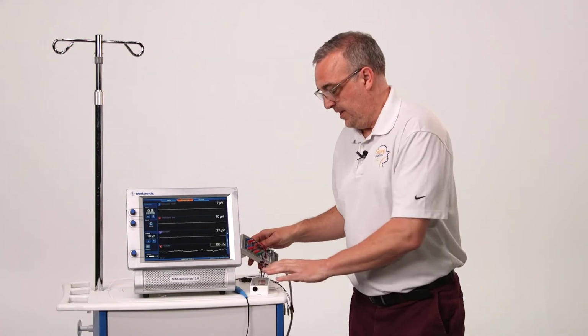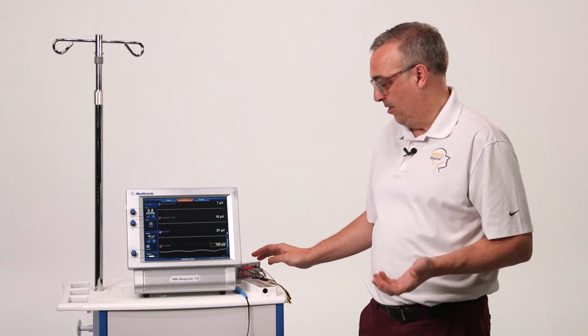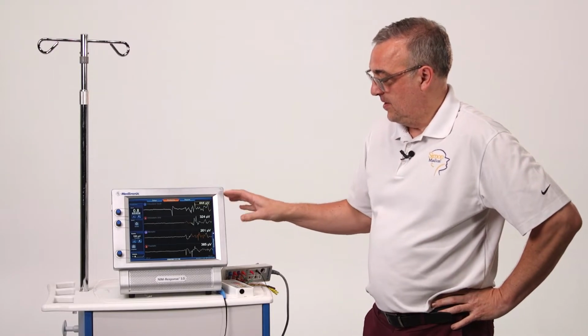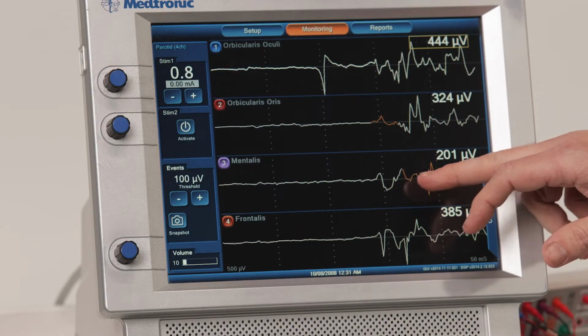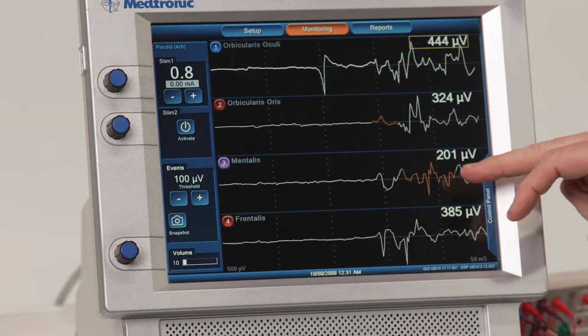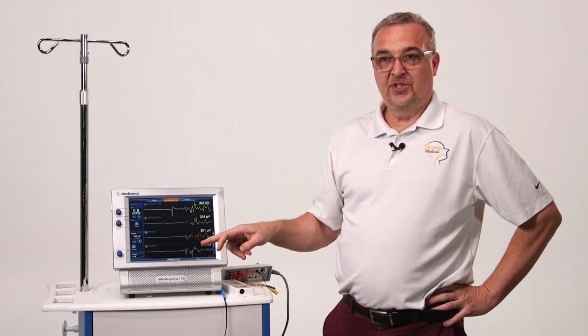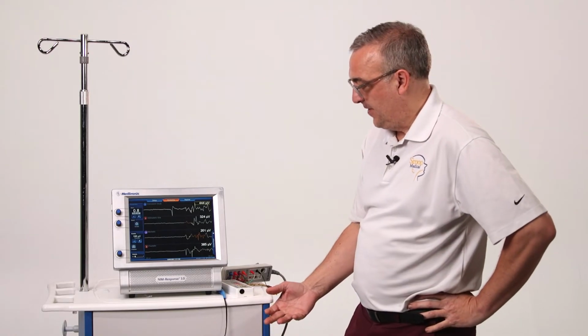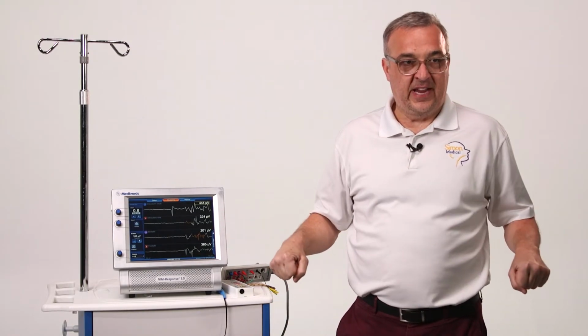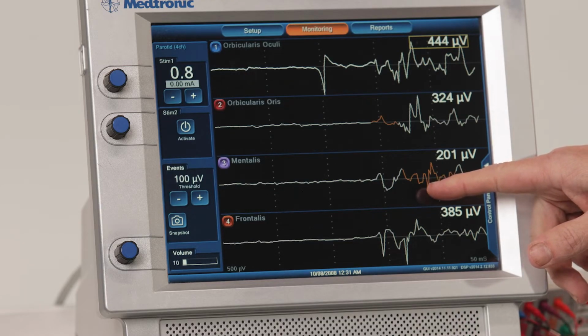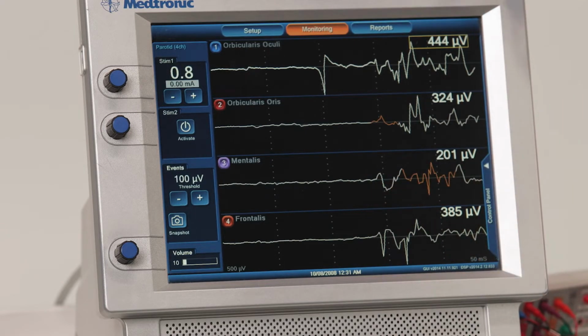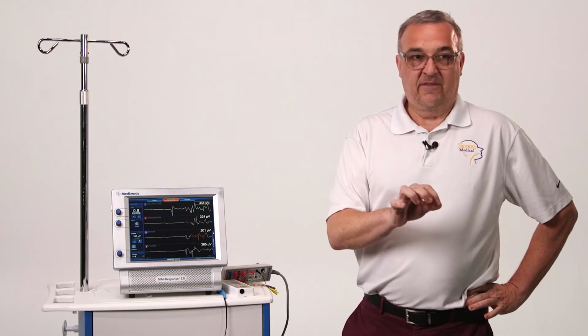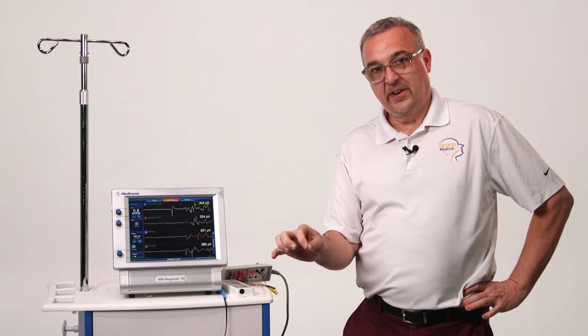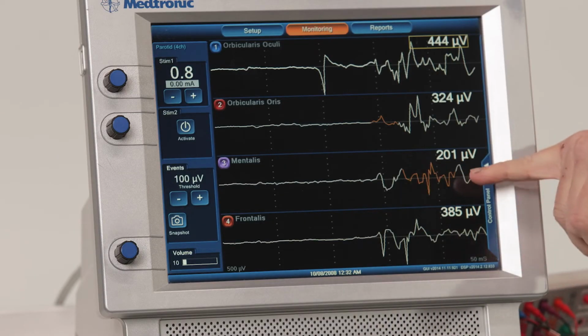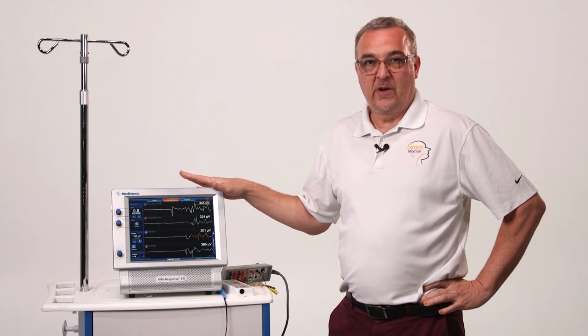So the NIM 3.0 is the only NIM that has what they call artifact detection. So it's kind of an AI algorithm. I wanted to give you an example of artifact detection. You've seen our software here has marked this in orange. So it's ruling this out as artifact and not genuine EMG response, likely far-field artifact or manipulation with instrumentation. It errs on the side of it being real response to be safe. So you're not getting necessarily false negatives, you're getting false positives. So when you see an orange waveform, it's artifact, okay? And that's something that's specific to the NIM 3.0. So I wanted to mention that.